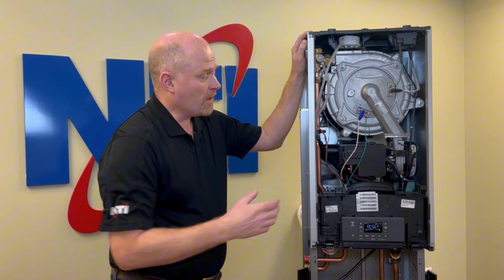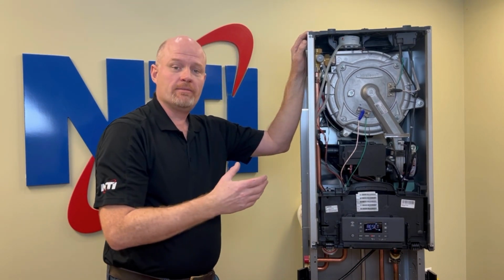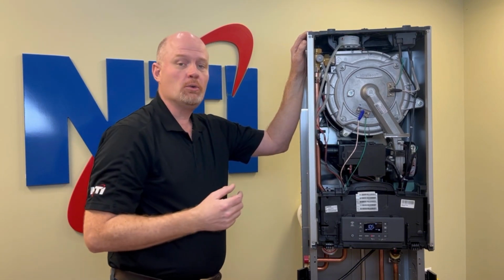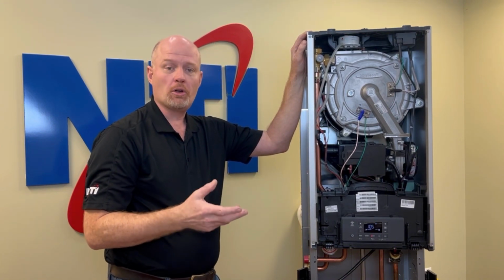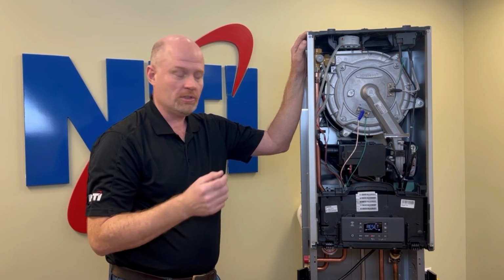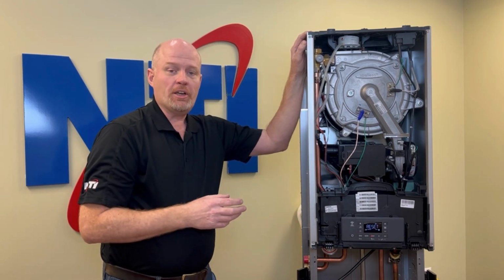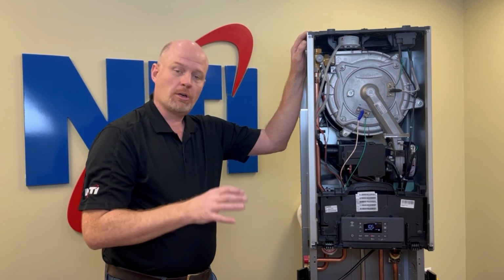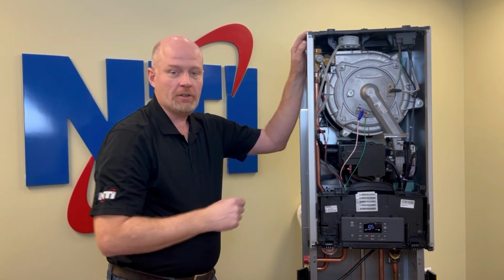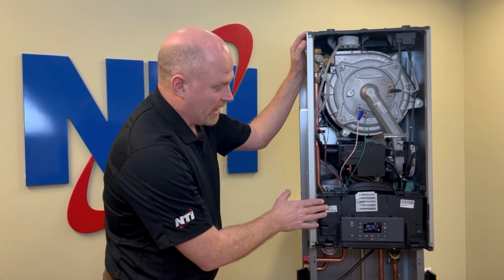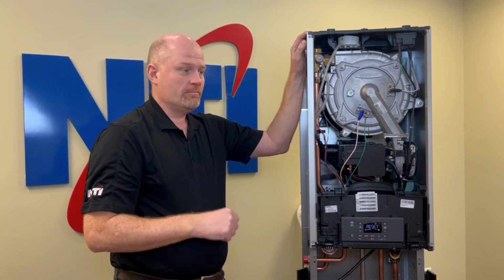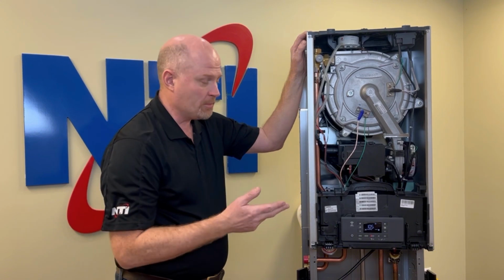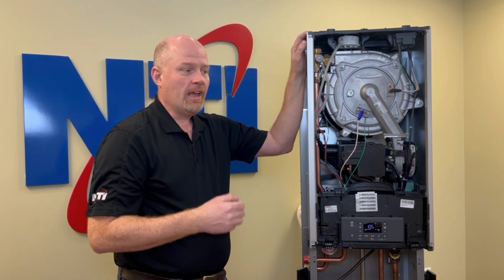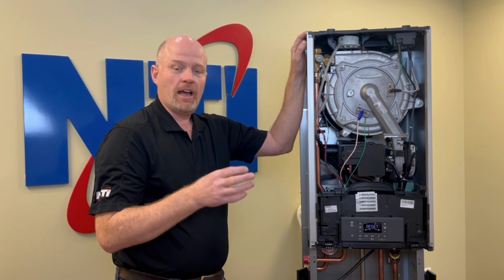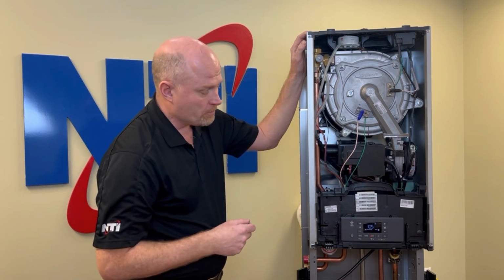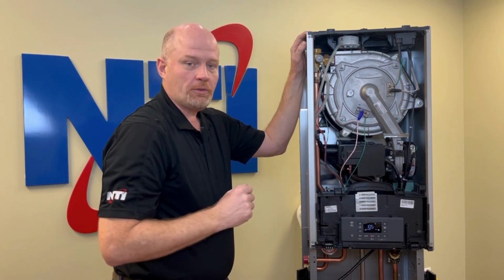If you have an error code 105 and you've noticed that the boiler is very hot and you have overheat codes including 1P1, 1P2, 101, 104, 103, 102, I would recommend that you check out our video on error code 101 because all of the troubleshooting in that video will cover everything you need to look at for this. But in brief, air in the system, a failed circulator, a plugged up plate exchanger or indirect tank, possibly a sensor failure, could all contribute to getting a 105 code. Effectively, it means there's a lack of water flow in the system.